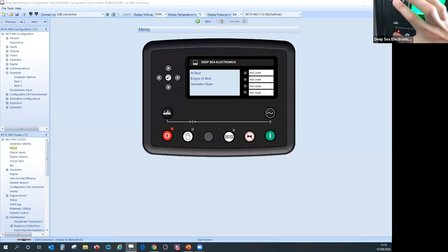Scroll through to the generator page. Perhaps I might want to change the topology, at the minute it says single phase 2-wire. If I press the tick button, I can change that to 3-phase 4-wire, then press the tick button. Once I've finished, I press and hold the tick button, and it goes back to the main page.